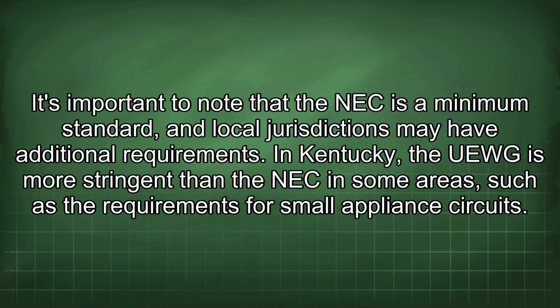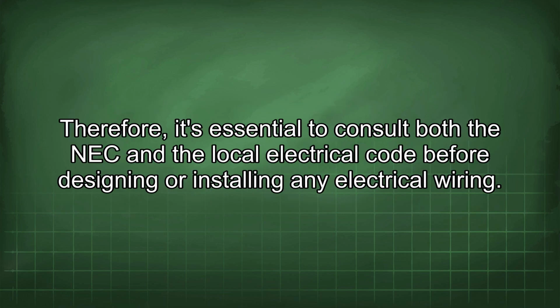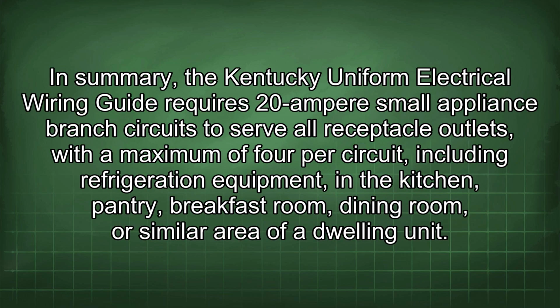It's important to note that the NEC is a minimum standard and local jurisdictions may have additional requirements. In Kentucky, the UEWG is more stringent than the NEC in some areas, such as the requirements for small appliance circuits. Therefore, it's essential to consult both the NEC and the local electrical code before designing or installing any electrical wiring. In summary, the Kentucky Uniform Electrical Wiring Guide requires 20 ampere small appliance branch circuits to serve all receptacle outlets, with a maximum of 4 per circuit, including refrigeration equipment, in the kitchen, pantry, breakfast room, dining room, or similar area of a dwelling unit.